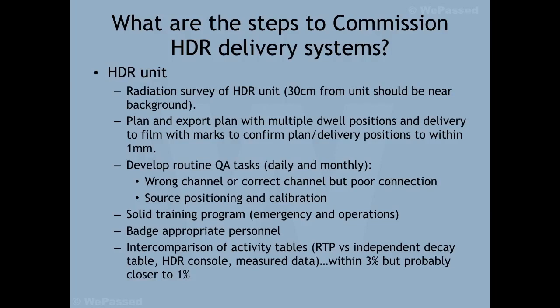Generally, you need to test if you have the wrong channel, you should have the interlock. If you have the correct channel but you do not connect the catheter, you should also have an interlock. Something like that, you need to test with the morning QA.